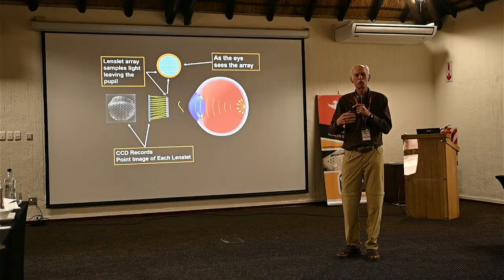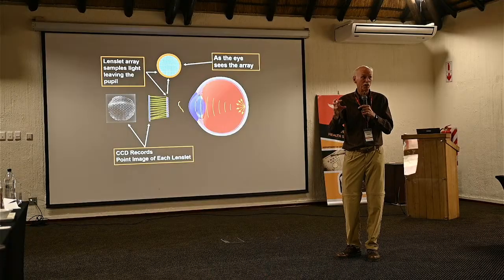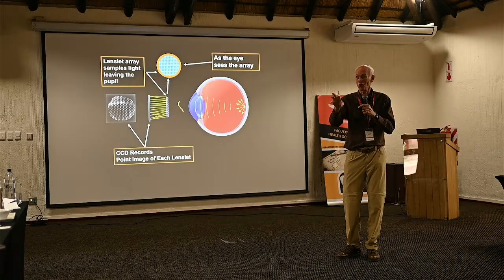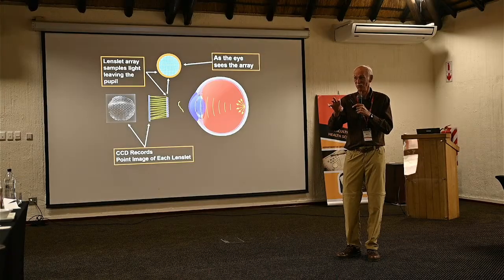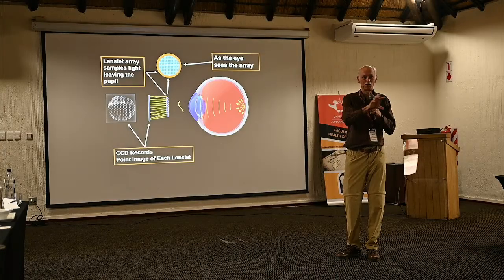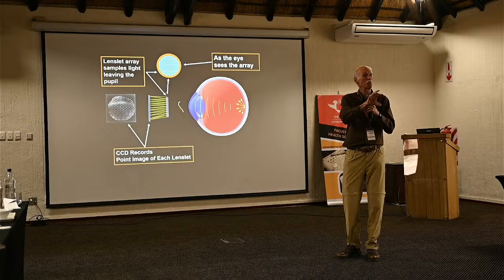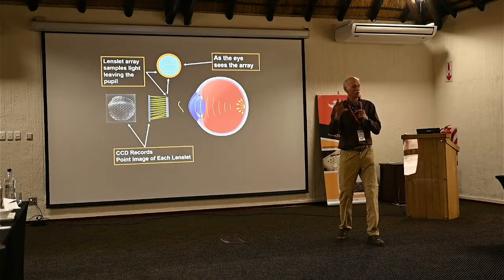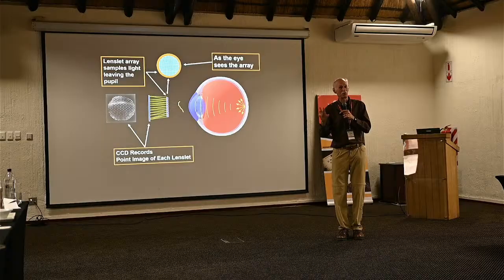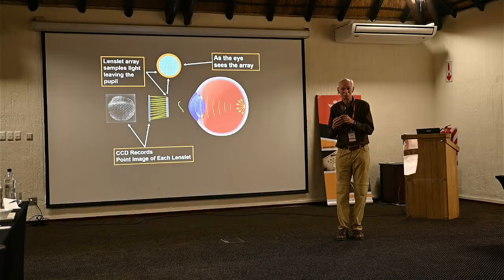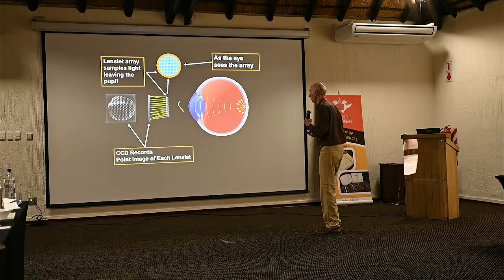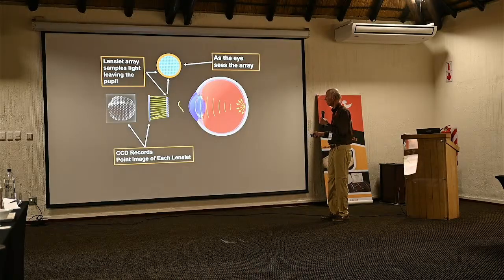The more modern version will actually have a second camera that takes a picture of the iris. And now it says, okay, now we know where the pupil is. The iris camera tells us, and it's got to be well registered with the data camera so the spots can be overlaid on top of the actual pupil of the iris. And now you've got a more reliable machine. One of those potential problems that you can spot if you understand the principles of what we're doing here.